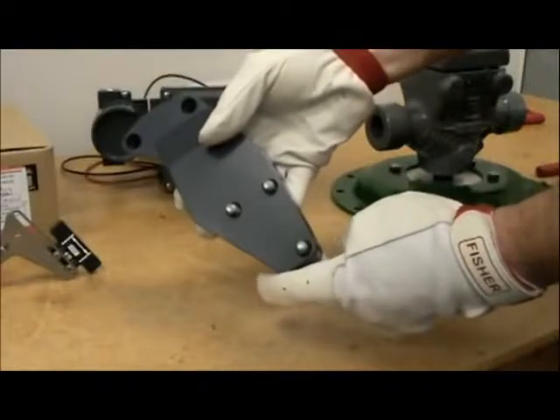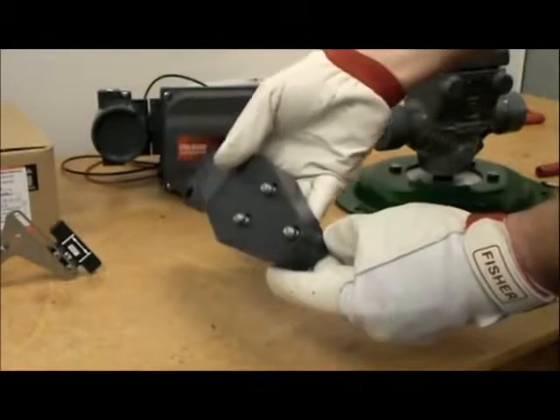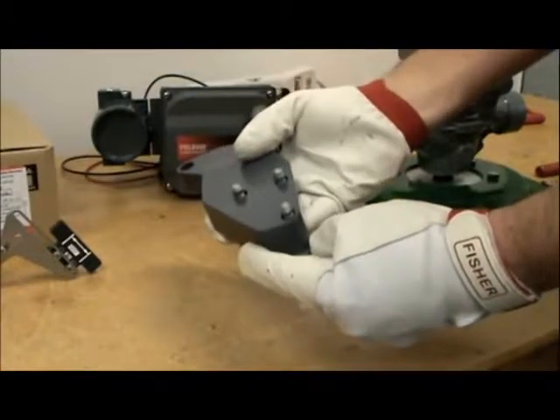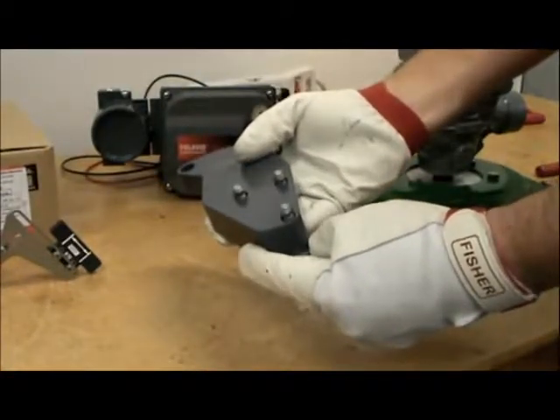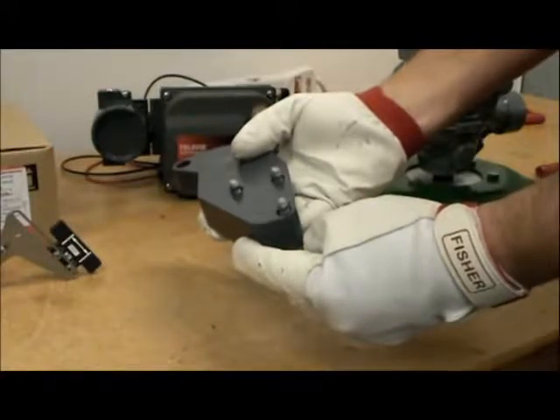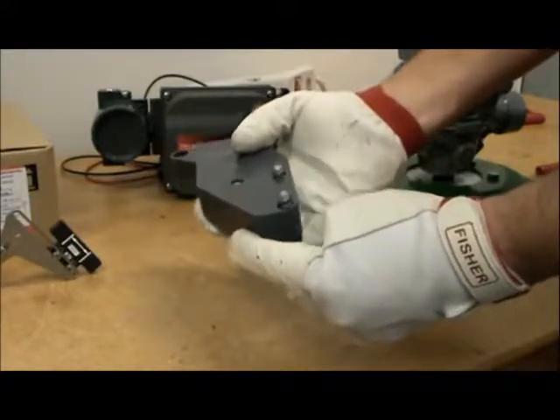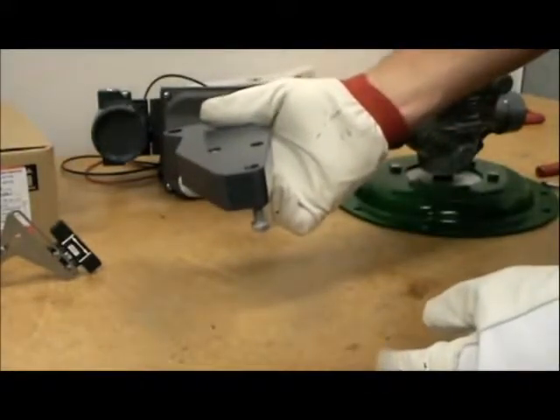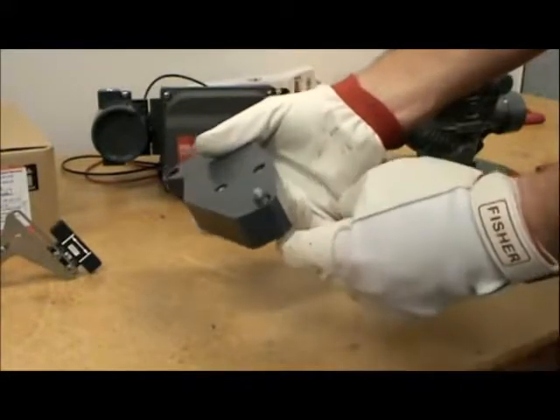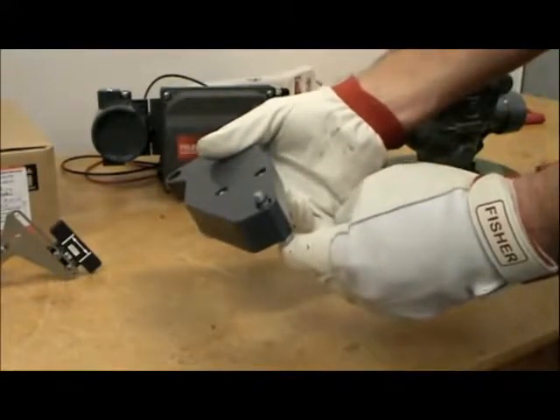Another sub-assembly that can be done ahead of time is to add O-rings to the three bolts which hold the DVC-6200 onto the mounting bracket. The O-rings hold the bolts in place and keep them from falling out. Install the O-rings just about a quarter of an inch onto the bolts.